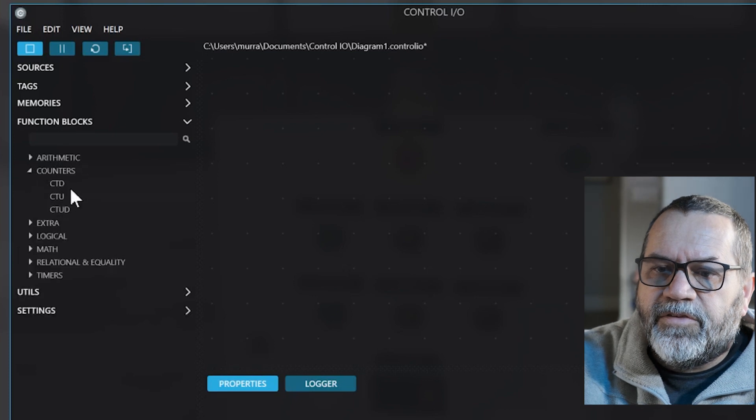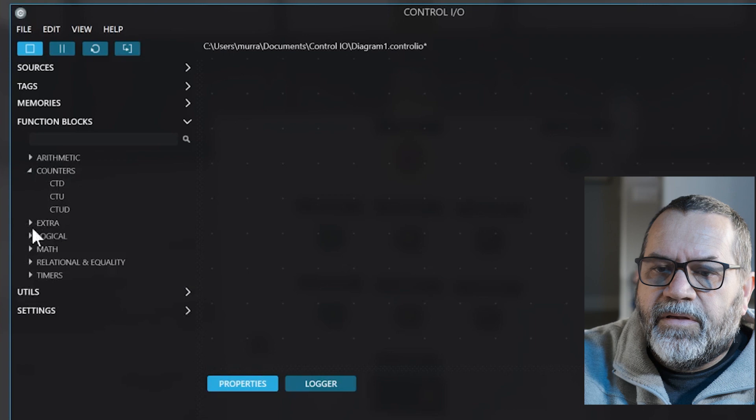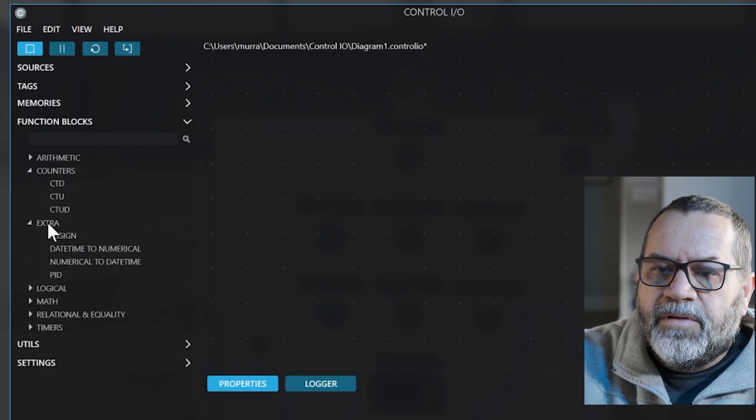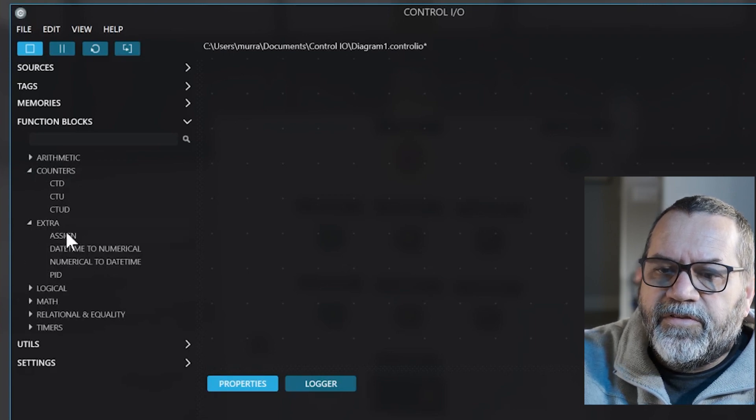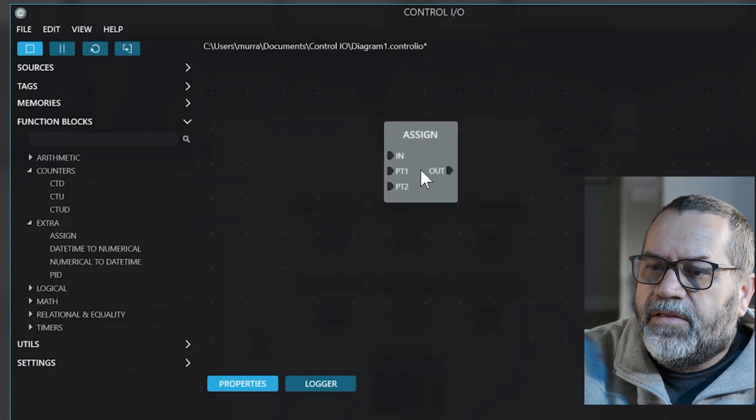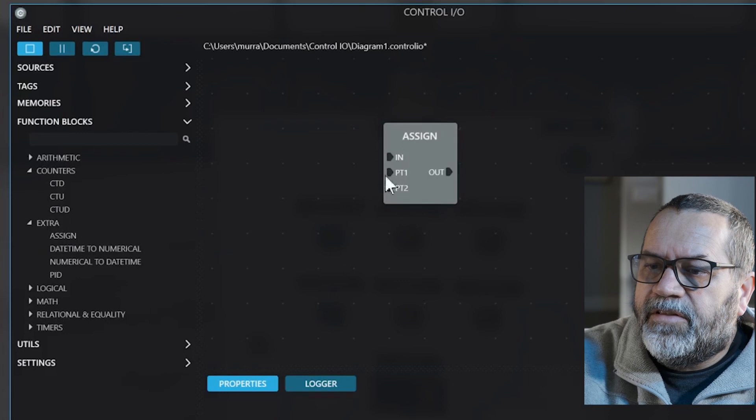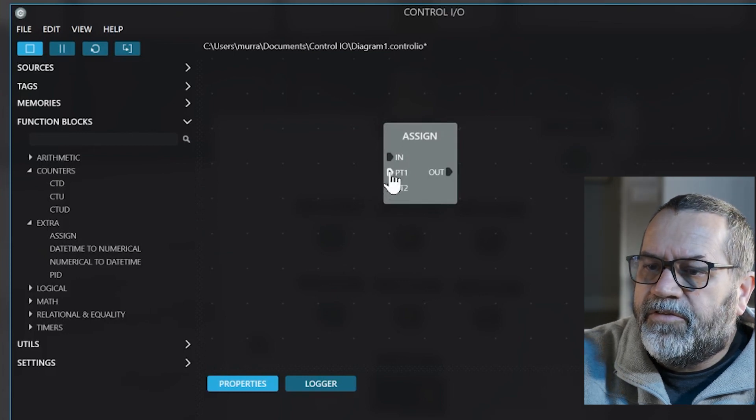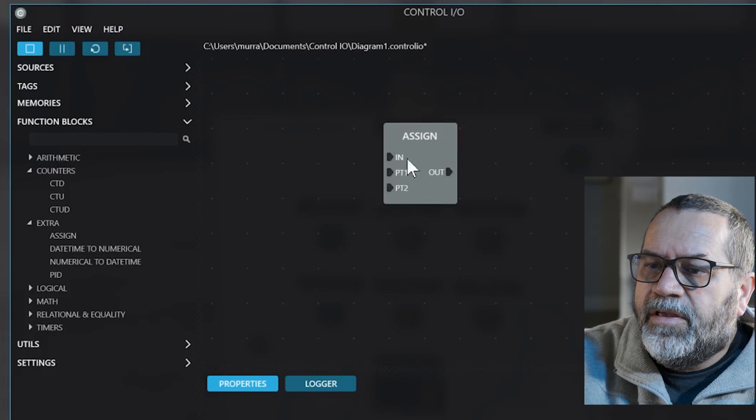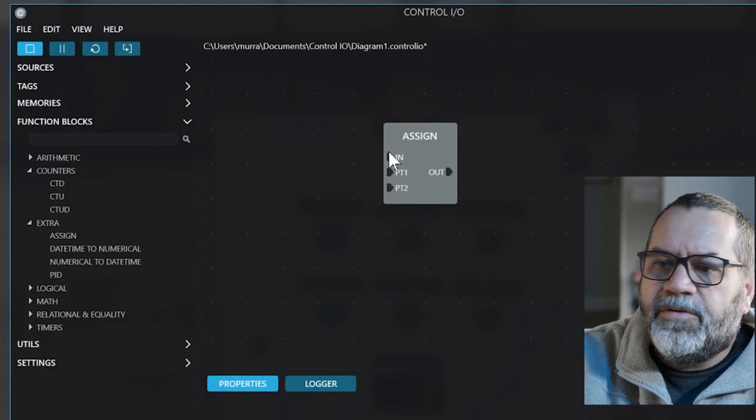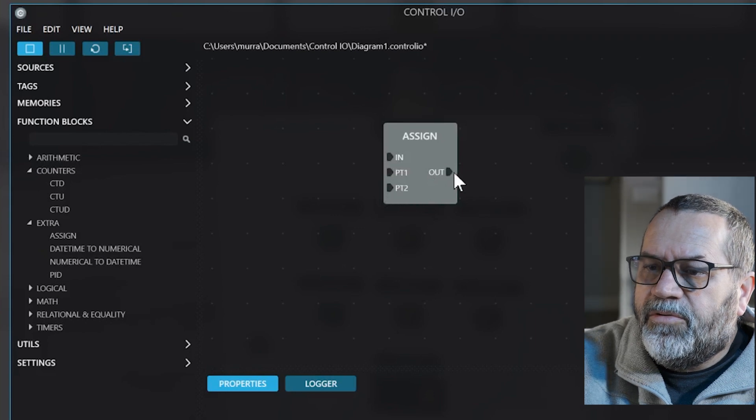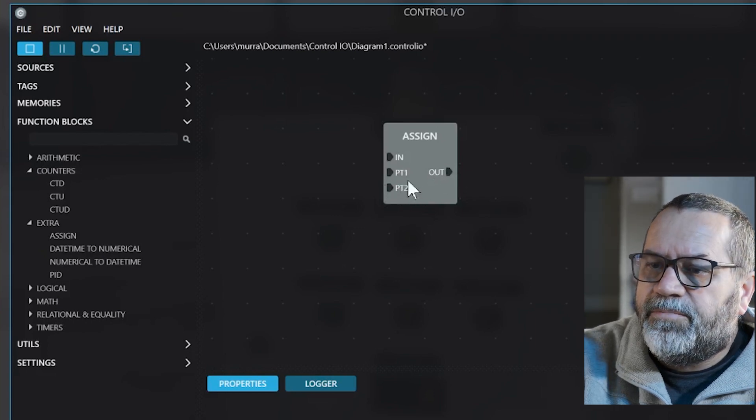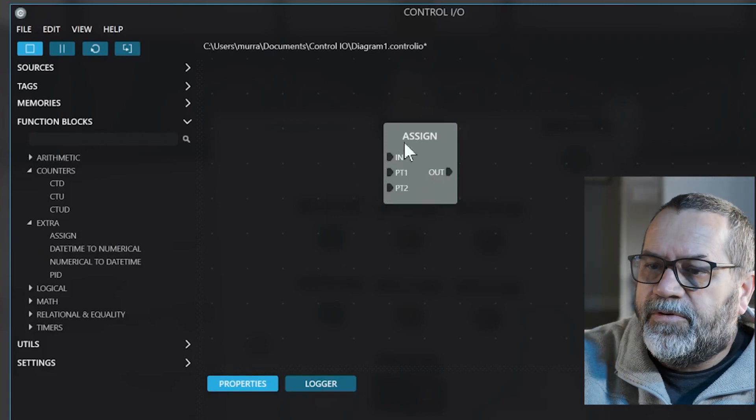Counters, that's for counting up or counting down. Extra we don't use too much. We might use this assign guy once in a while and it's kind of neat. I can send two different values. Say I send a 5 to this and a 10 to this, and if I send a hot signal to this guy then it'll send the PT2, and if I don't send a hot signal it'll send out the PT1. So sometimes that's kind of helpful.